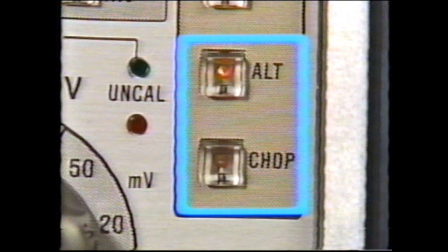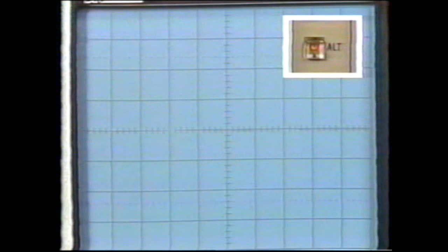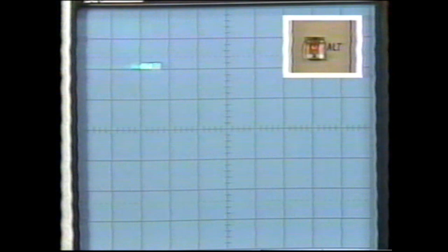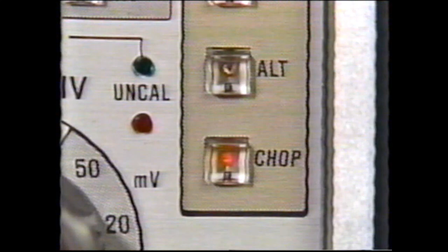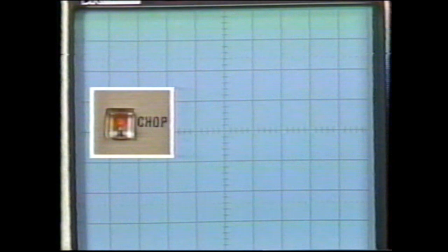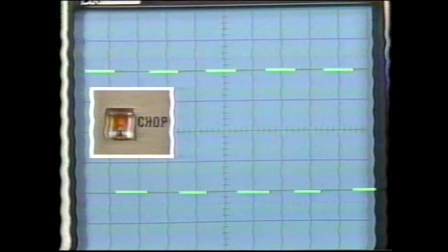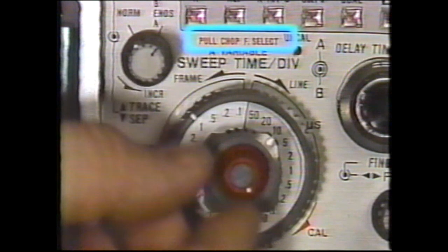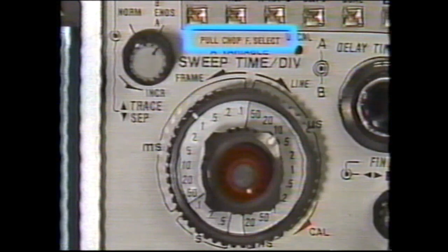In addition, there are 2 modes of switching the CRT beam between 2 input channels: alternate and chopped. The alternate mode is used for viewing high-frequency or high-speed waveforms of 1 millisecond per division and faster. In the alternate mode, first channel 1 is swept, then channel 2. The chopped mode is used for viewing low-frequency or low-speed waveforms of 1 millisecond per division and slower. The sweep is chopped at approximately 250 kilohertz and switched between channel 1 and 2. The pull chop frequency select control permits better viewing of the signal when it approaches the chop frequency level.